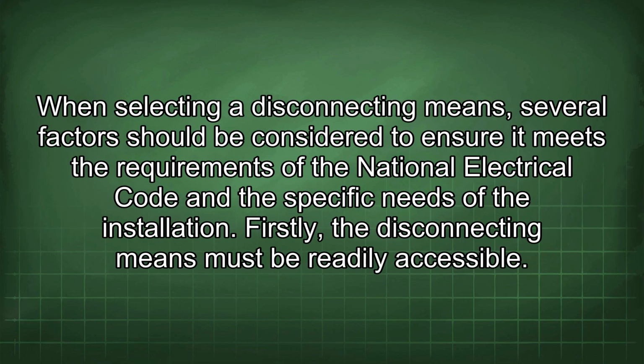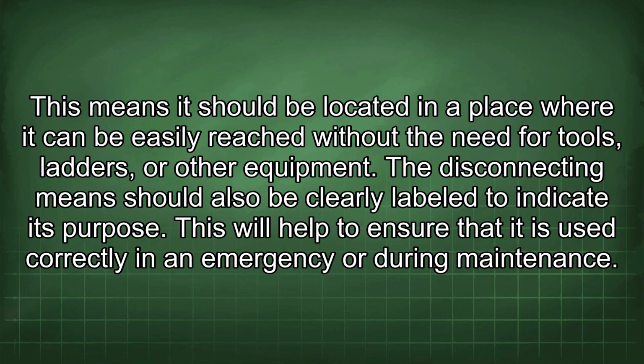When selecting a disconnecting means, several factors should be considered to ensure it meets the requirements of the National Electrical Code and the specific needs of the installation. Firstly, the disconnecting means must be readily accessible. This means it should be located in a place where it can be easily reached without the need for tools, ladders, or other equipment. The disconnecting means should also be clearly labeled to indicate its purpose. This will help to ensure that it is used correctly in an emergency or during maintenance.